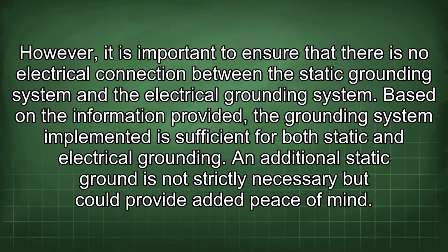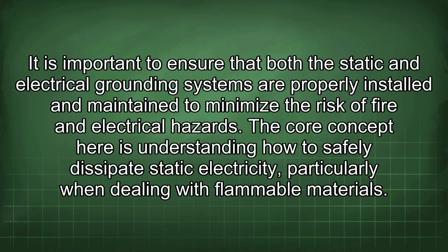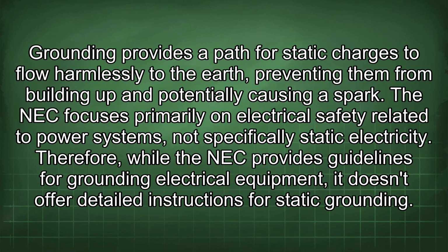An additional static ground is not strictly necessary, but could provide added peace of mind. It is important to ensure that both the static and electrical grounding systems are properly installed and maintained to minimize the risk of fire and electrical hazards. The core concept here is understanding how to safely dissipate static electricity, particularly when dealing with flammable materials. Grounding provides a path for static charges to flow harmlessly to the earth, preventing them from building up and potentially causing a spark. The NEC focuses primarily on electrical safety related to power systems, not specifically static electricity.